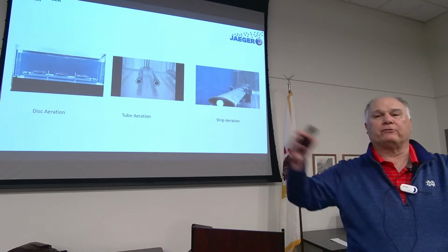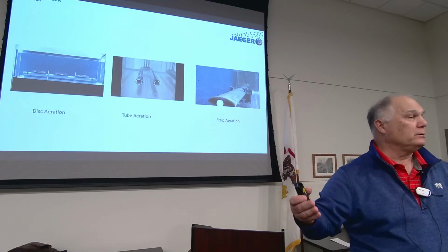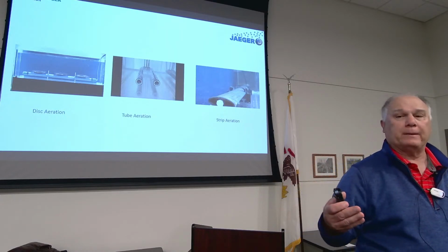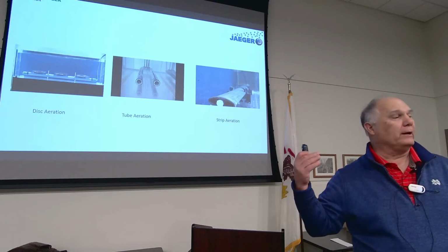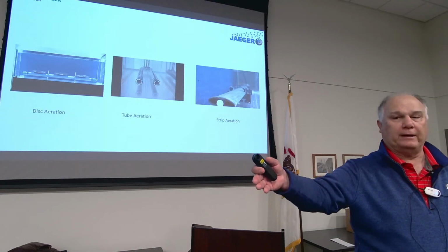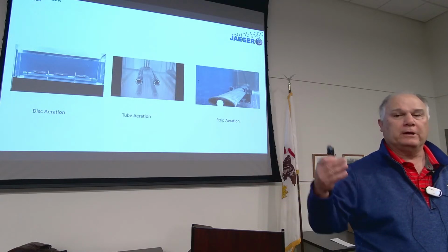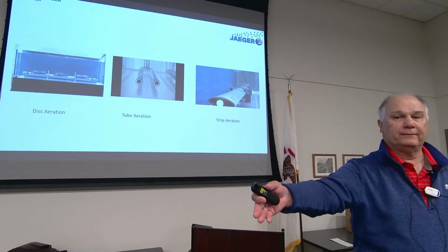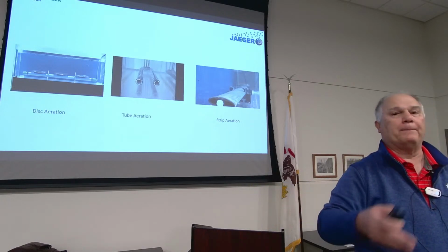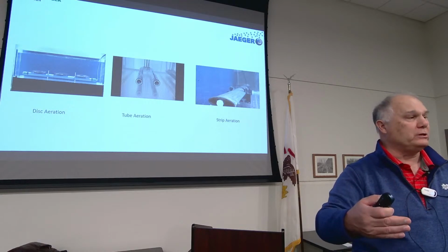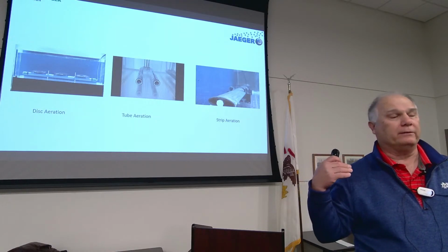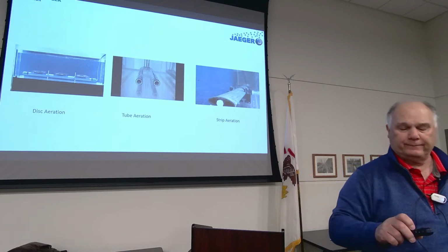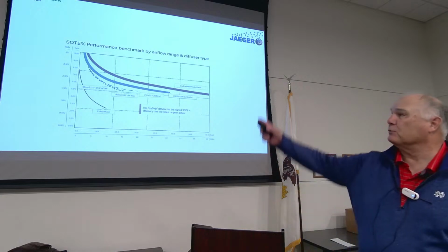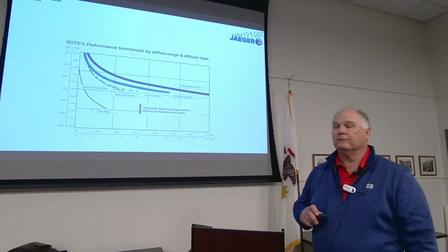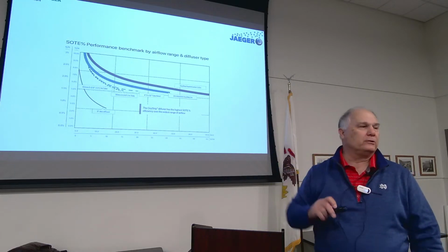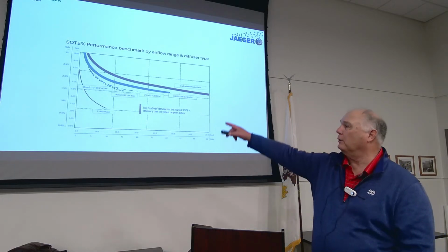So as we went from the left to the right, what happens is that we get more efficient and higher membrane surface area, active membrane surface area. So one product to the right is worth 9 products to the left, 9-inch discs. So one strip is worth 9 discs. So from that perspective, we're starting to now get a better product, and we're getting 15% more efficiency because the bubbles are smaller on the far right with the strip than they are on the left with the disc. That's what this curve shows. So this curve shows a 9-inch disc, which is the standard in the industry and has been since we invented it 60 years ago, is right there.